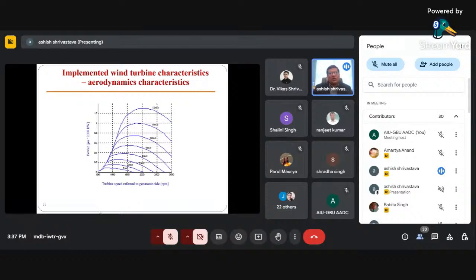This is another graph, which is known as the aerodynamic characteristic of the wind turbine. It is also a graph between turbine speed on the generator side in RPM and the power on the y-axis. And here 2000 kilowatt is considered as 1 per unit. Now you can see this graph is again drawn for different wind speeds, starting from 5 meter per second to 12 meter per second. Again, you can see at a lower RPM, at a lower turbine speed, you are not able to achieve the maximum. The maxima is achieved somewhere close to the midway.